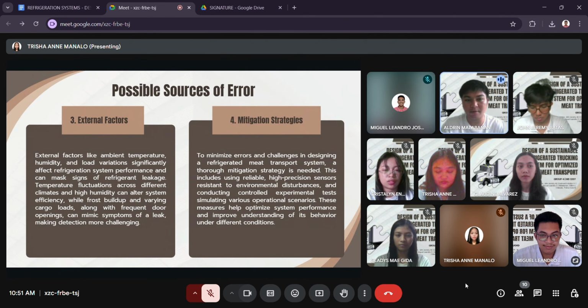External factors like ambient temperature, humidity, and load variation significantly affect refrigeration system performance and can mask signs of refrigerant leakage. Temperature fluctuation across different climates and high humidity can alter system efficiency, while frost buildup and varying cargo loads, along with frequent door openings, can mimic symptoms of a leak, making detection more challenging.